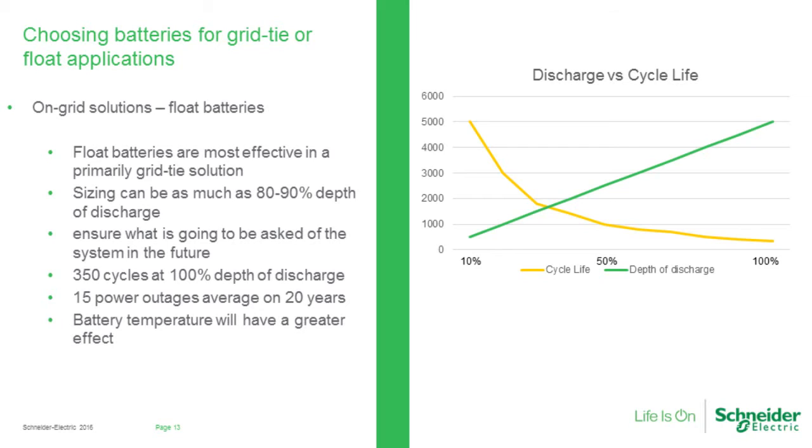before they cycle out. One thing that's worth noting within the research that I did for this presentation is battery temperature actually had a huge relationship on how those batteries survive. Even float life batteries can have a shortened life if the batteries aren't kept at about 20 degrees C or lower. Anything higher than that, and we start affecting the battery's overall life as well. So when designing a system, think about putting it in a place where it is fairly temperature controlled. An outdoor garage that gets up to 90 degrees in the wintertime or in the summertime may be a little too warm a place for those batteries. You may need to look elsewhere or figure out a different way of storing those batteries.